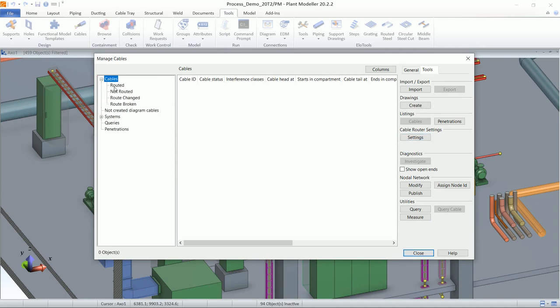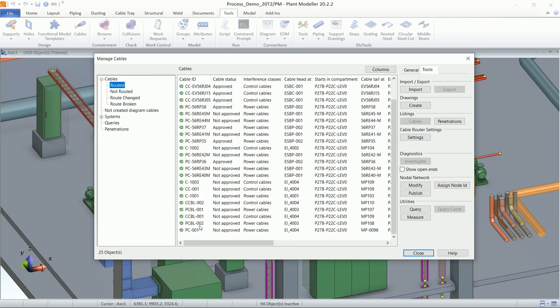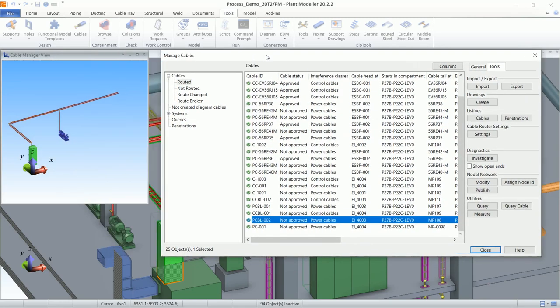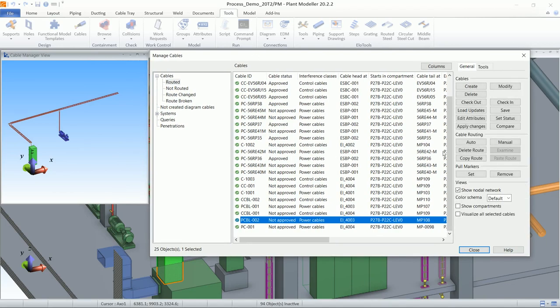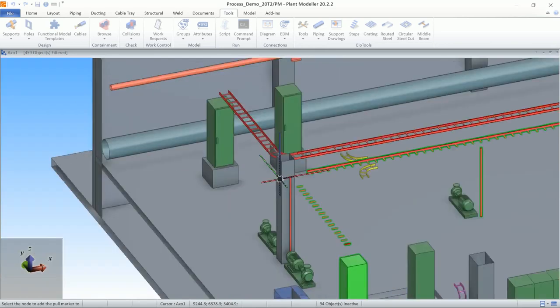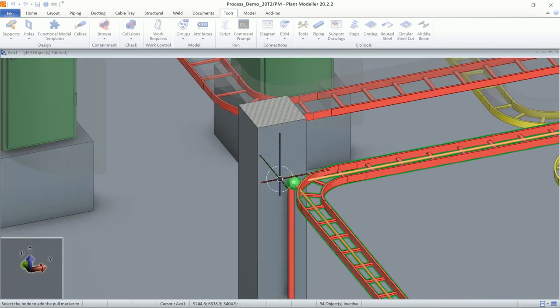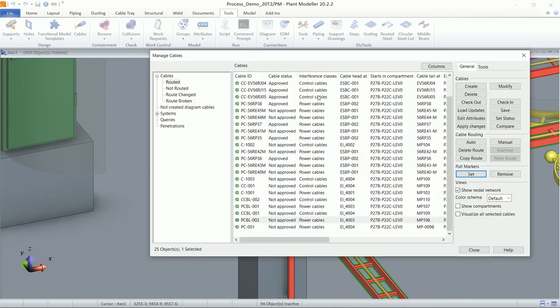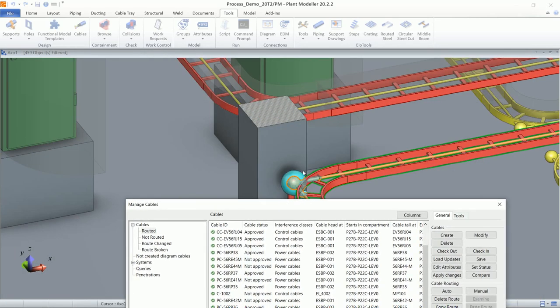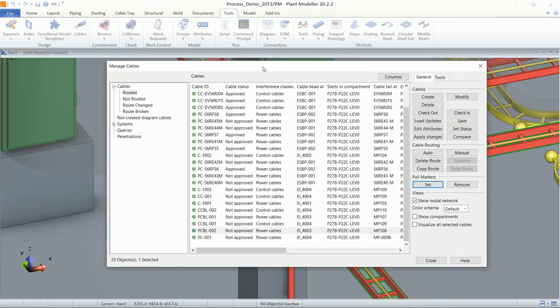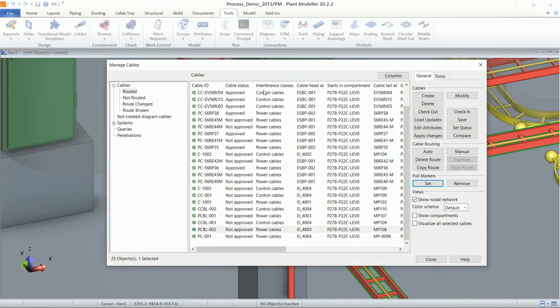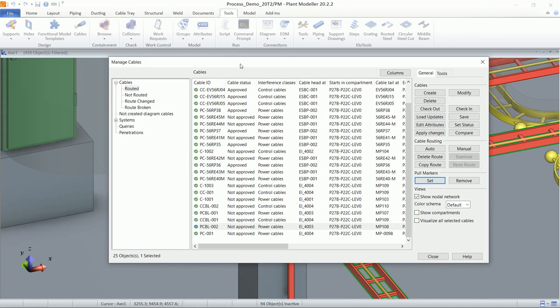Another feature in the cable router is the Pull Marker. A pull marker is a point from where the cable is delivered. To set it, click on a cable and select a node point in the cable's route as the pull marker. Once set, we can get the length from the pull marker to the head equipment and to the tail equipment separately.